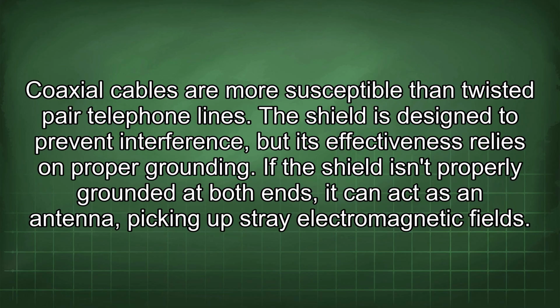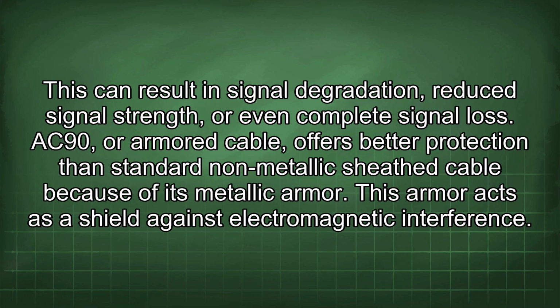Coaxial cables are more susceptible than twisted pair telephone lines. The shield is designed to prevent interference, but its effectiveness relies on proper grounding. If the shield isn't properly grounded at both ends, it can act as an antenna, picking up stray electromagnetic fields. This can result in signal degradation, reduced signal strength, or even complete signal loss.